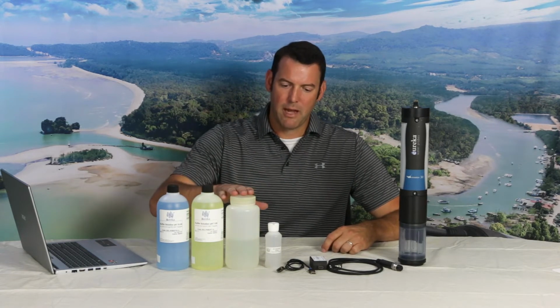Today we're going to talk about calibrating your pH sensor. It's pretty simple really. All you need are two of your favorite pH buffer solutions, some DI water, and your reference electrode electrolyte. Let's jump in. First of all, this is a good time to clean your sensors of any foreign material that could potentially affect your pH calibration.